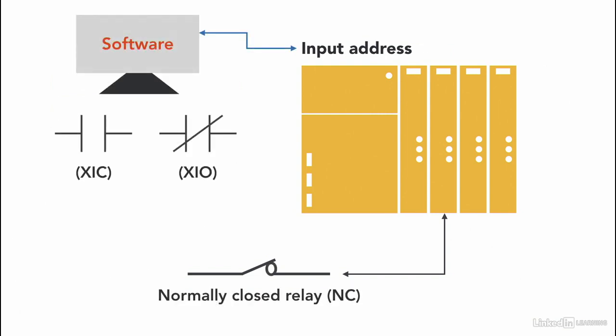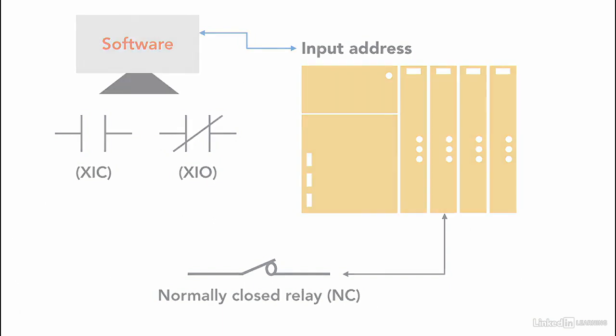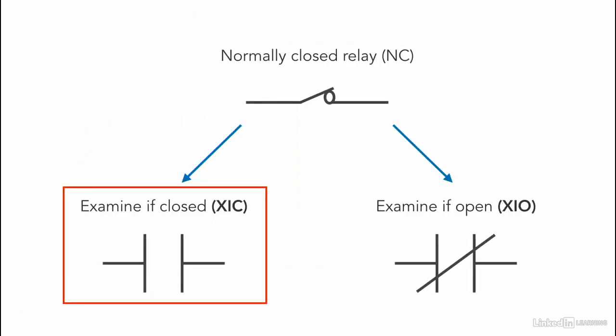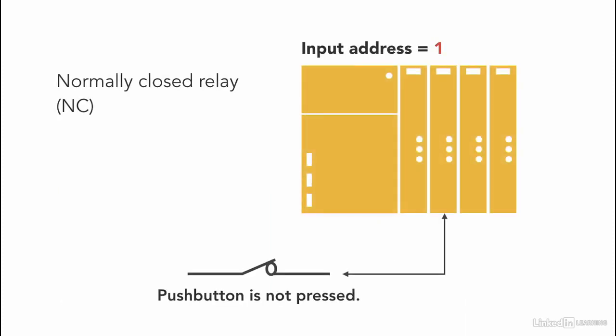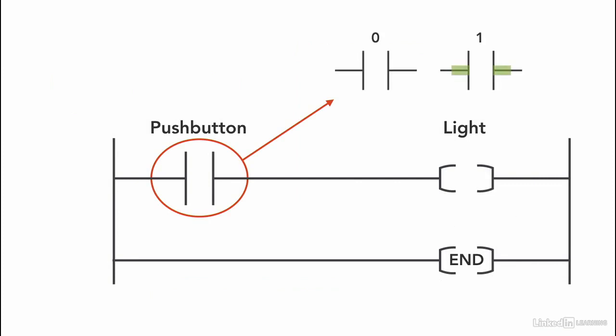Let's see what happens in the program when using two different instructions. Using XIC — remember, the XIC instruction is activated when the memory location is 1. So if the push button is not pressed, the memory location is 1 because it's a normally closed push button. Current is flowing, the XIC instruction will be highlighted, and the light will turn on without pressing the push button. Once the push button is pressed, the memory location is 0, and XIC is not activated anymore — it works the opposite way as a normally open contact.